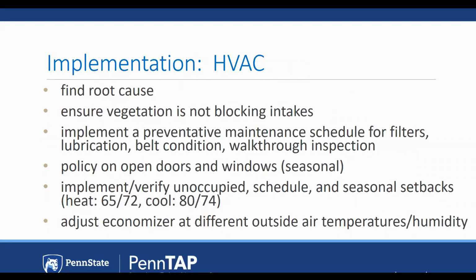For HVAC, you might have to find a root cause, but other alternatives include ensuring vegetation is not blocking the intakes, whether the vegetation is an actively growing bush or leaves that have fallen in autumn and you need to blow away that debris. Implement a preventative maintenance schedule for filters, lubrication, belt condition, and the walkthrough inspection. Set a policy on open doors and windows, which could be seasonal in your buildings. Make sure that you consider setbacks on your thermostats, and also adjusting your economizer during different weather conditions.